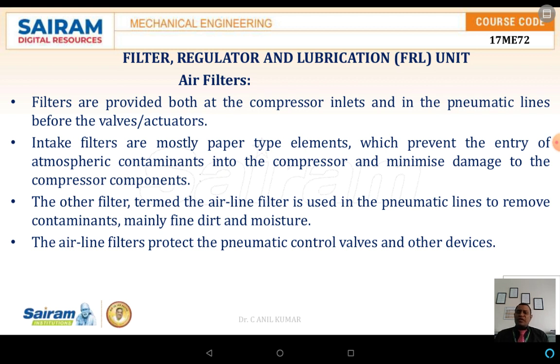These are the three basic elements which are required in the system. Filters are provided both at the compressor inlet and also in the pneumatic line before the valves or the actuators. The filters are needed to remove the dust particles from the air, and in some cases there may be a chance of humidity also. Those things should be removed from the air used in the system.